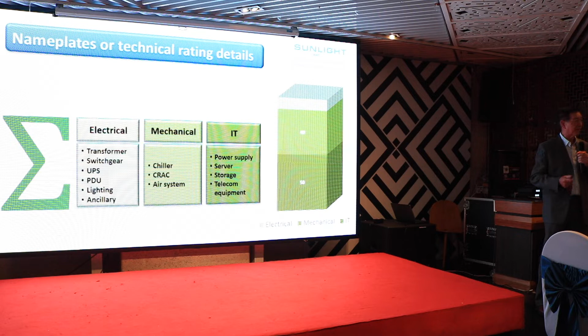The total power will consist of the total load that we have just summed up, the electrical, mechanical, and IT load. Then you have to add on the power for what level of redundancy you want, or your client wants.